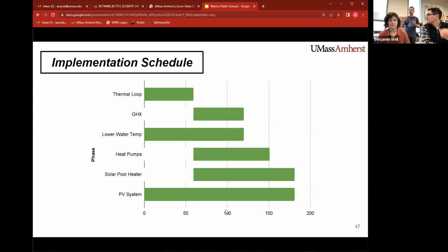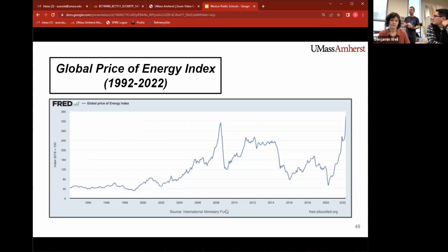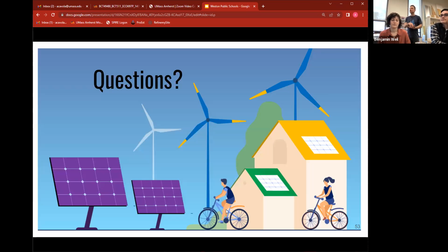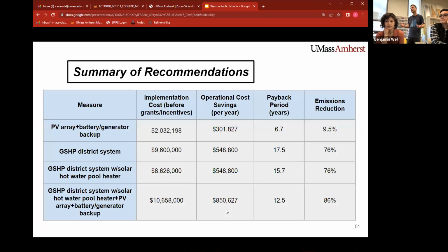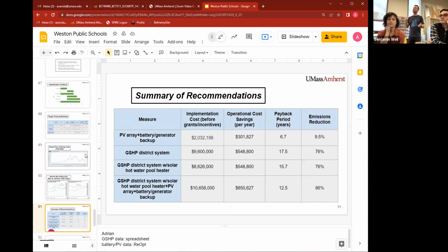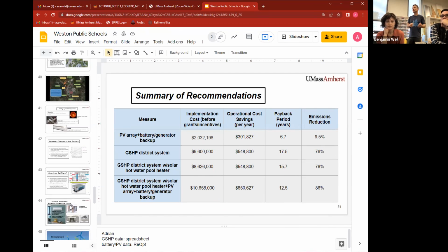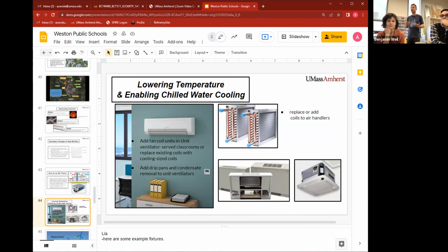I want to clarify on the existing heating systems and how they integrate. For the most part, you have hydronic heating systems and no cooling system. This proposal uses your existing piping. Most of these are 2-pipe systems, so you send around hot water. You'd use the existing piping and heat emitters, plus some additional fan coil units, clipping out radiation where you don't have the ability to collect condensate. That allows you to use the same system for heating and cooling. In 2-pipe systems, unlike 4-pipe systems, you can't do simultaneous heating and cooling, you have to switch from one to the other, but that's still better than what you have now.